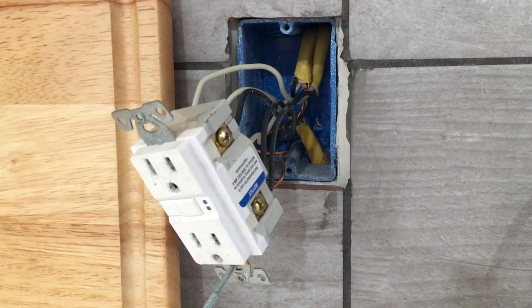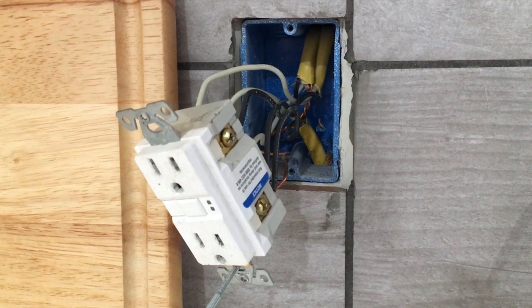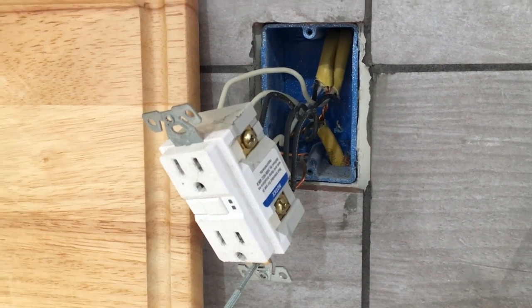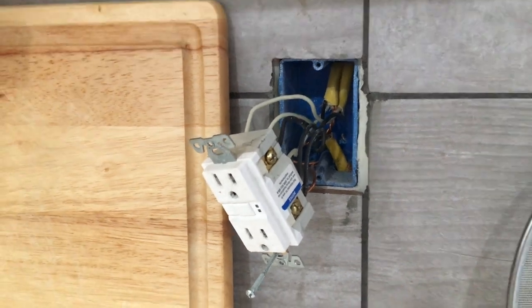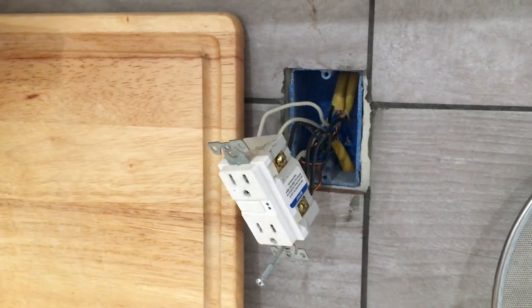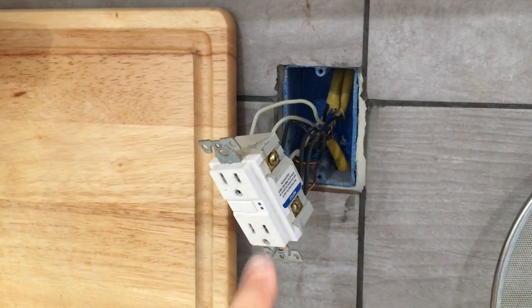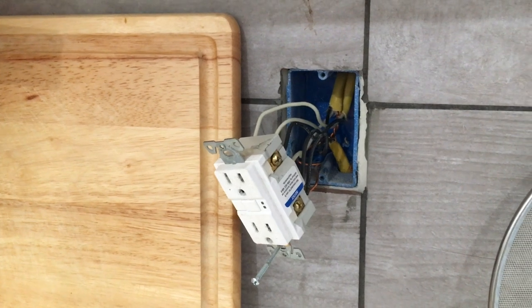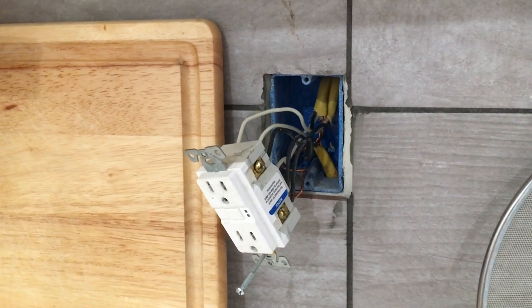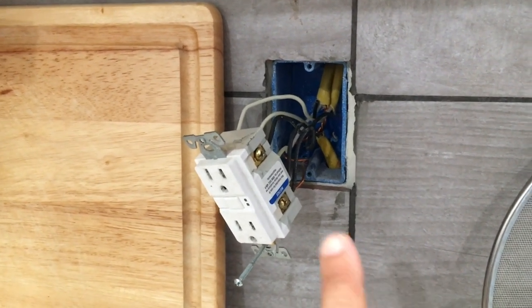Looking at the blue electrical box, we have three cables: one on the bottom and two on the top, left and right. This GFCI outlet is being fed power on the top left cable, which is coming from an ordinary electrical outlet on our left side, and that ordinary outlet is being powered by a 20 amp breaker from the electrical panel.